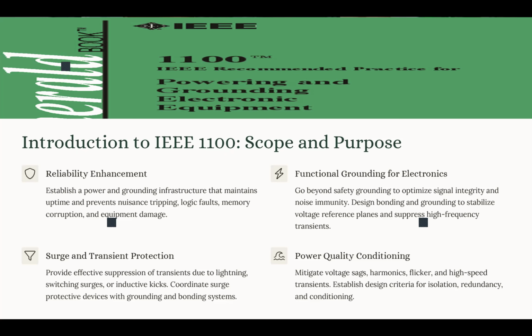Now, we also need to have a stable voltage reference to make sure of the proper functionality of sensitive electronic systems, which we do by bonding and grounding the system and designing those grounding systems in a way that maintains a consistent reference plane. And it should happen across all the interconnected devices in our system. Now, we said this standard adds functional grounding to the safety grounding. So we need to also design our grounding system and power distribution system for safety too.